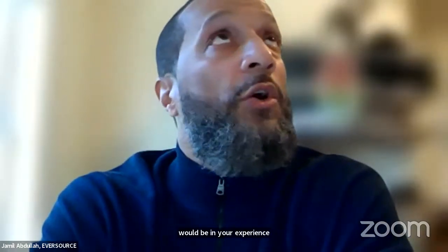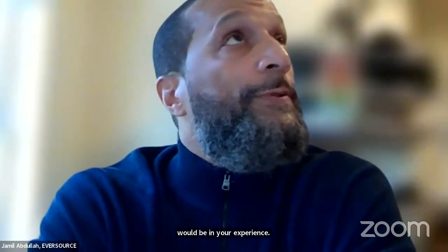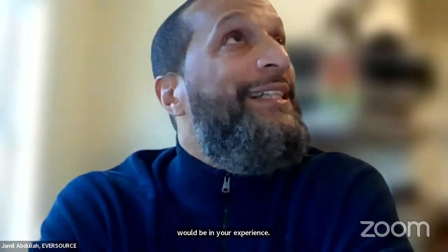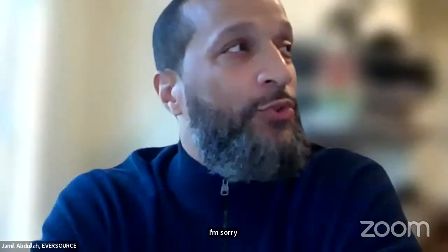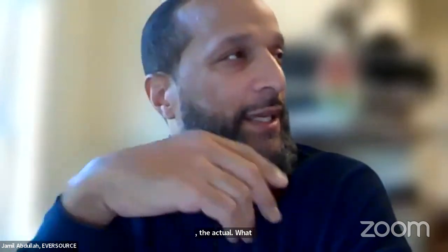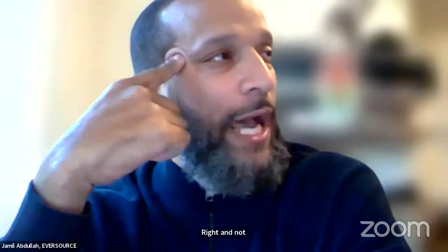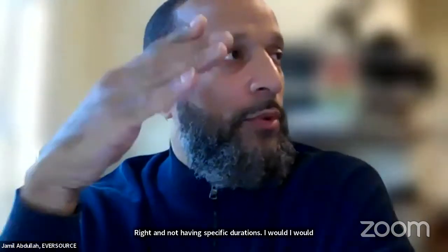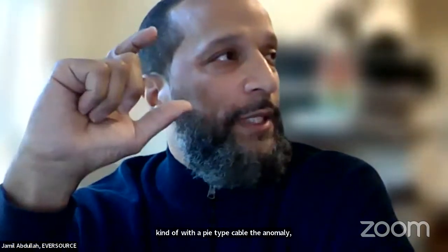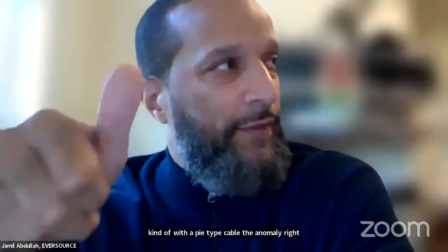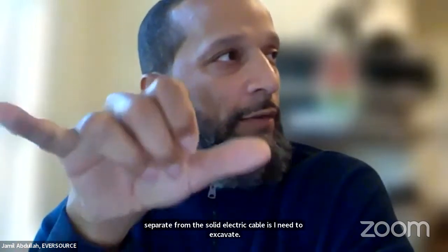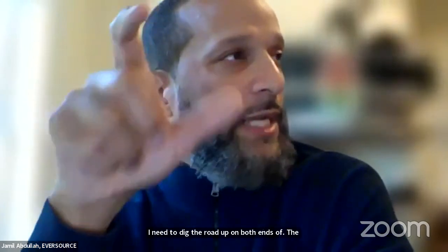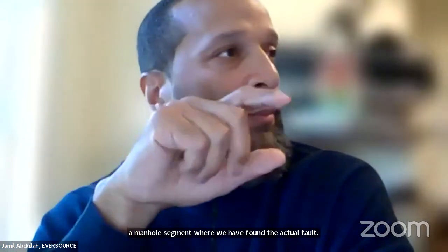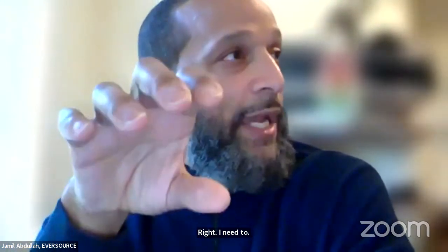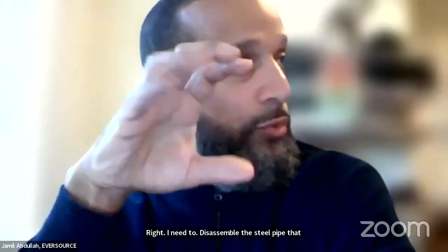Yeah. So the actual durations, if I were to think about it comparatively, and not having specific durations, with a pipe type cable, the anomaly, separate from the solid dielectric cable, is I need to excavate. So I need to dig the road up on both ends of the manhole-to-manhole segment where we have found the actual fault. I need to disassemble the steel pipe that's surrounding the splice, like cut through the steel pipe.